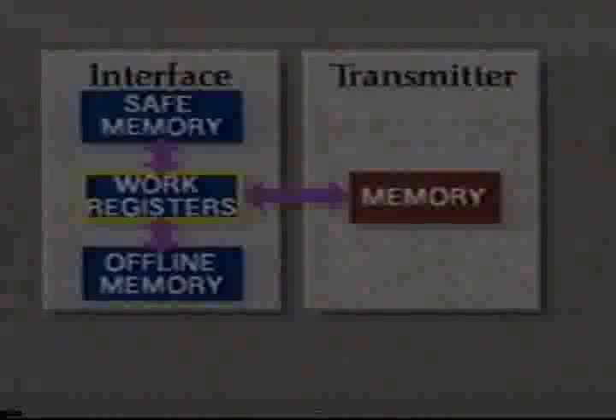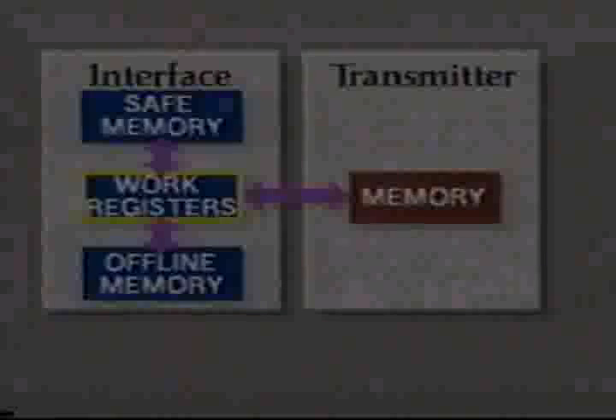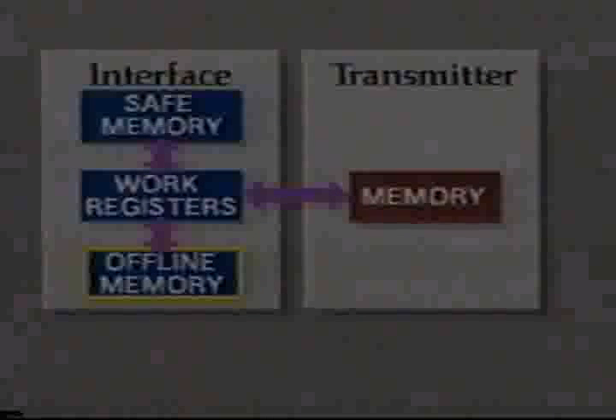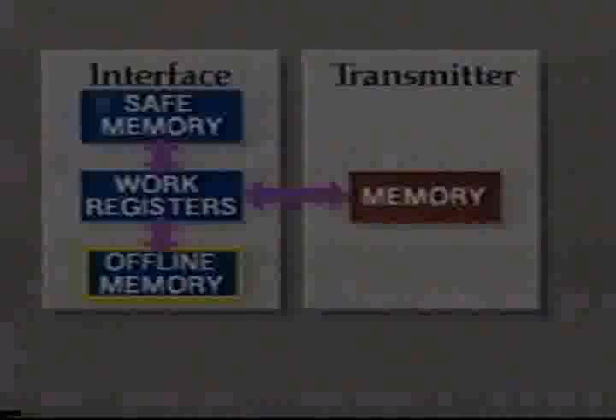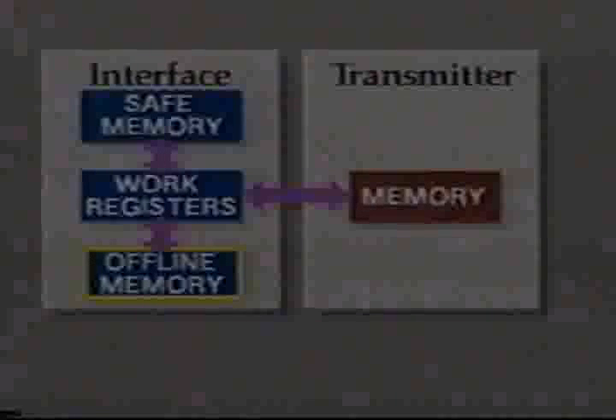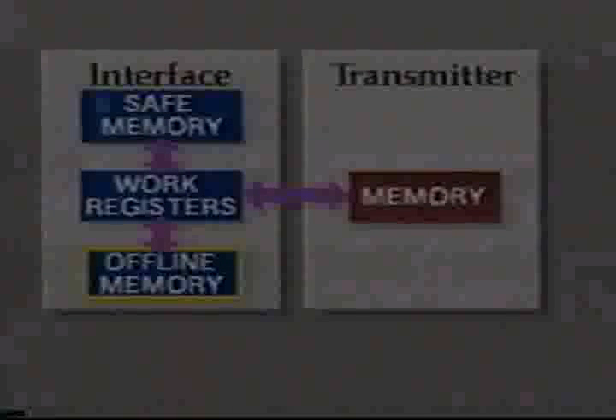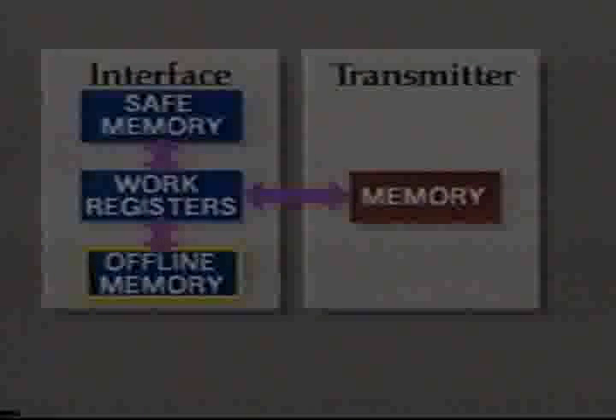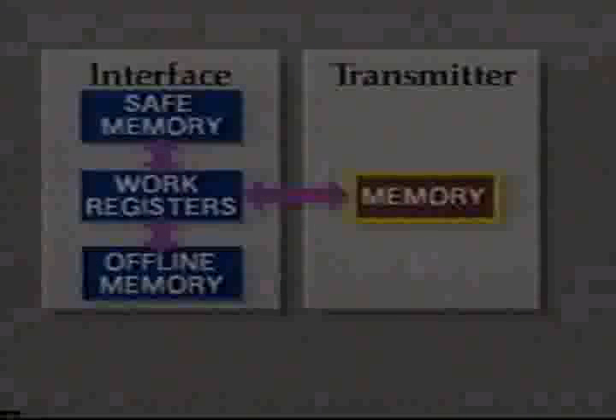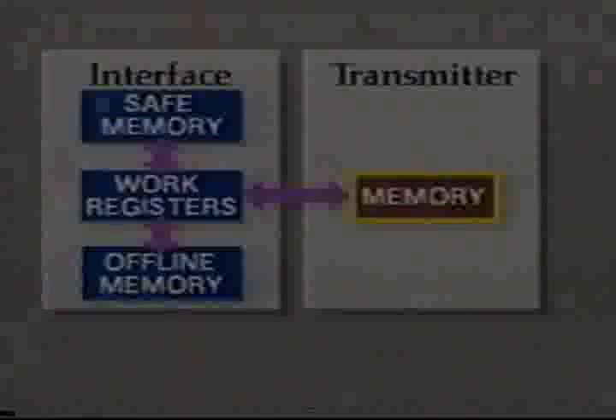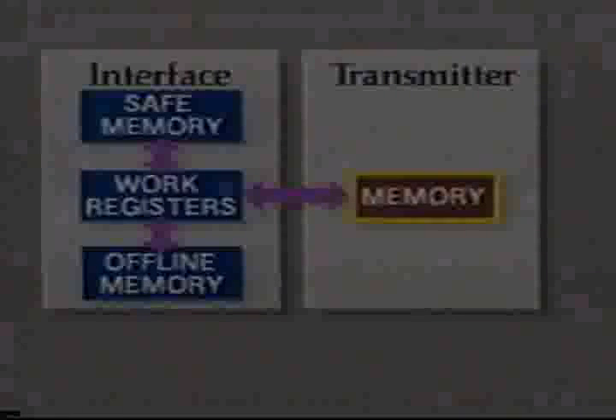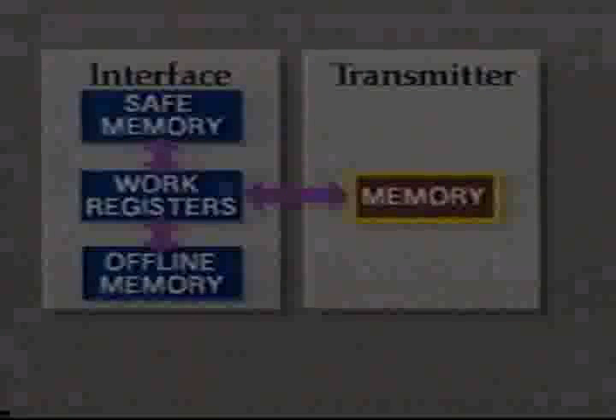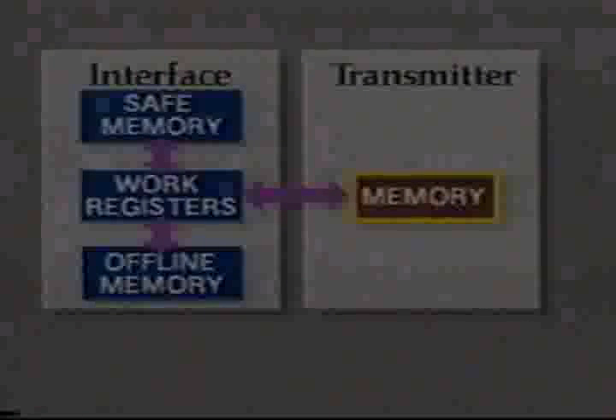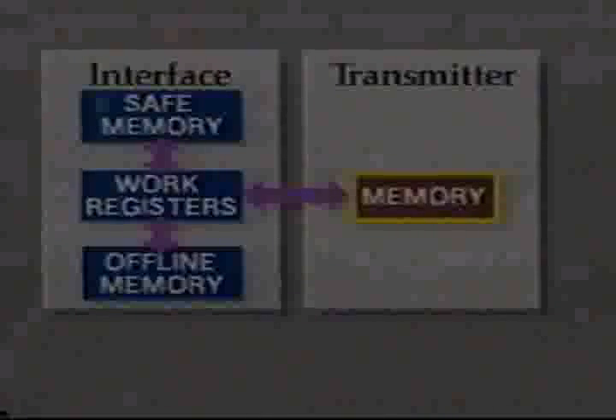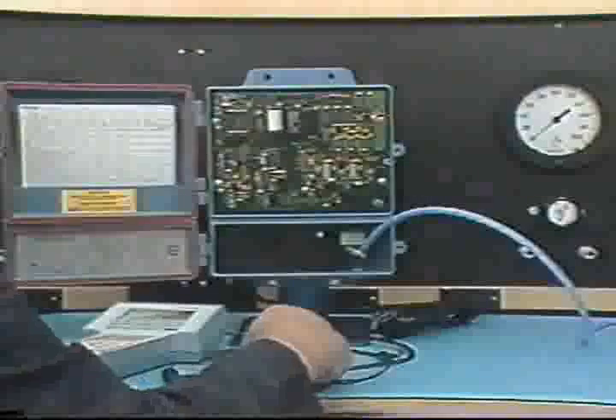The work registers are the actual location in memory where the data is stored. This memory location stores configuration information that was previously entered into the interface for downloading to a transmitter. The offline memory is non-volatile. The transmitter memory stores the data that's downloaded from the interface to the transmitter. This data is never accessed directly. It must be uploaded to the work registers first.